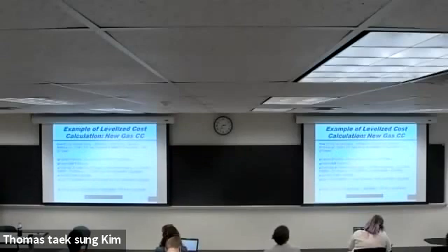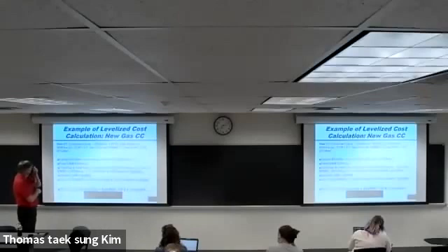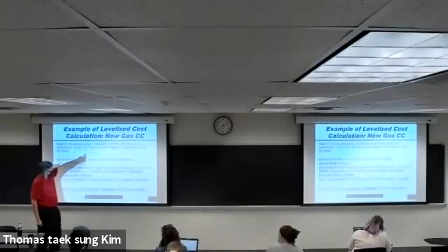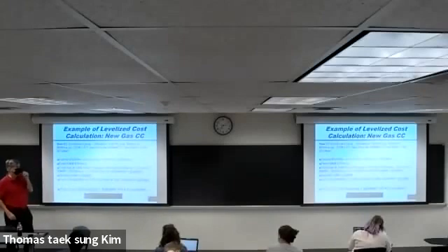All right, so let's take, as I mentioned, a levelized cost calculation for a new gas combined cycle. In this one, we're going to assume it's going to operate at a 68.5% capacity factor. Why did I pick that capacity factor? Well, because I wanted to keep the math easy. And so that works out to 6,000 hours a year. I like round numbers when we do these. And the capital charge rate is 10%. The gas price we're assuming is $4. Actually happens to be right around $4 now. That was lucky.